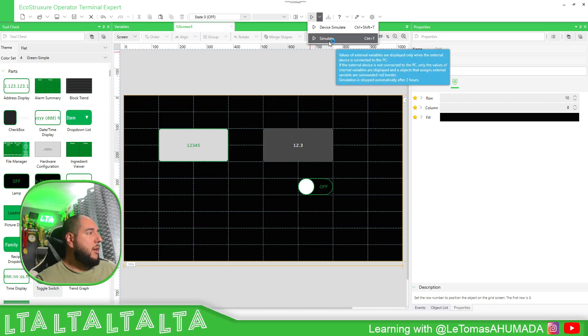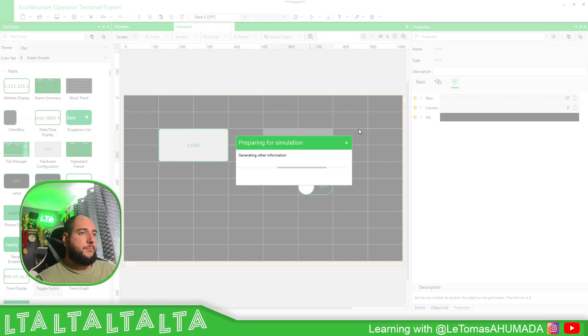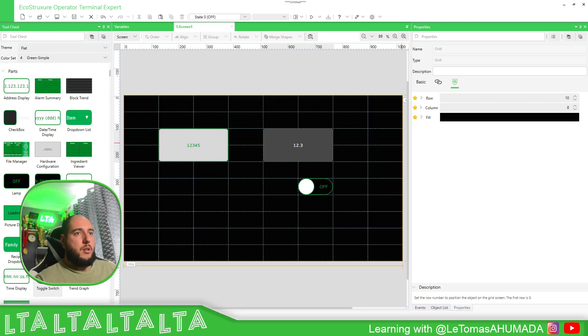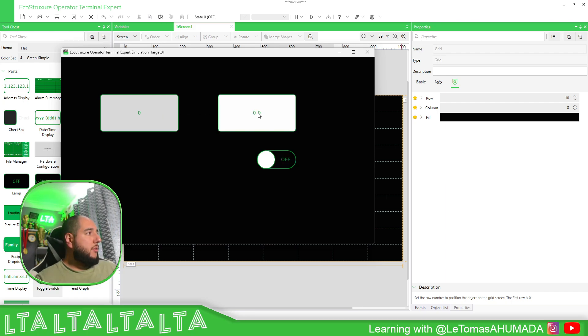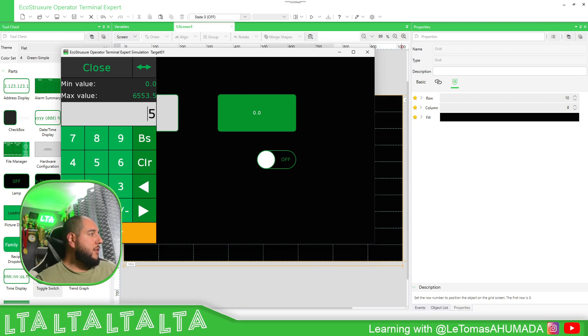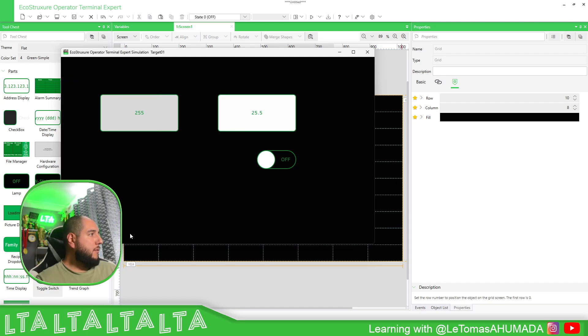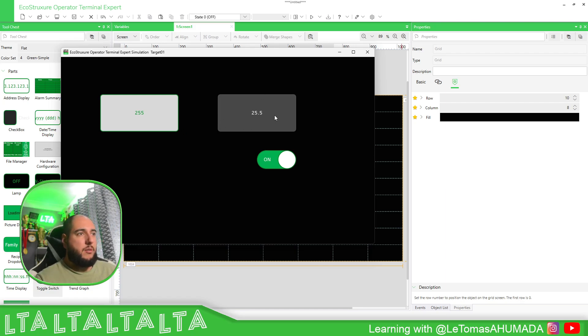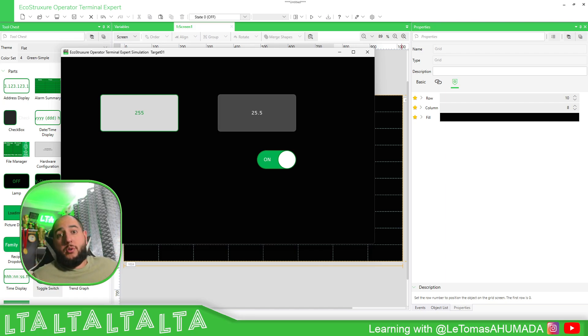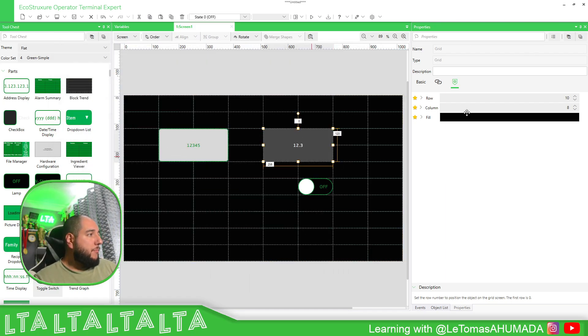Let's simulate and see what happens. Here the interlock is on, so I'm not able to change anything — I'm clicking, trust me, but nothing happens. If I disable this I can enter a value like 20.5. And if I block it again, the interlock is back. This is how you can block a field — it could be linked to a value from the PLC so that during a specific part of the process, nobody can change it.